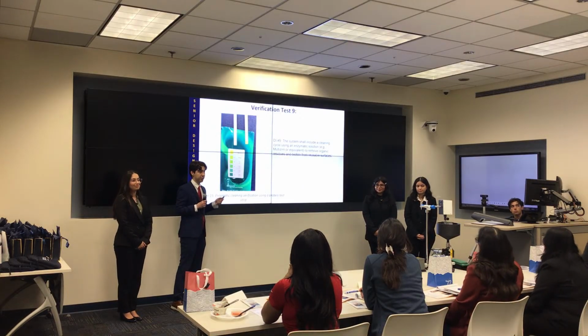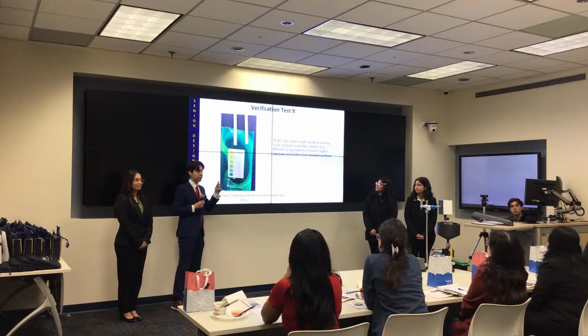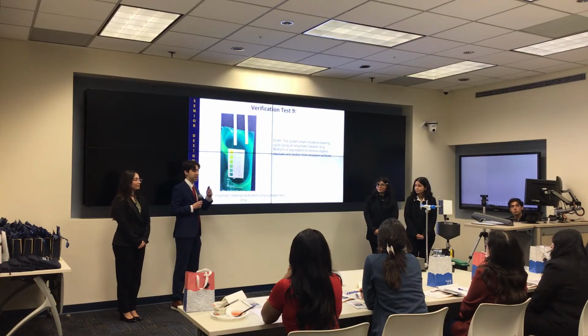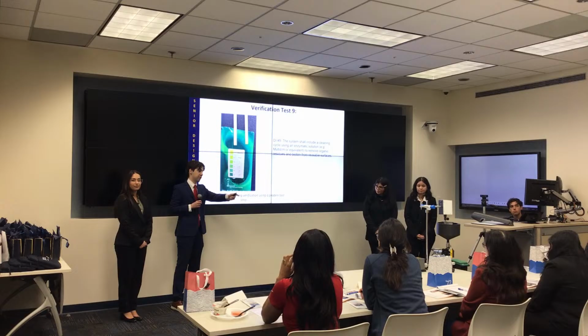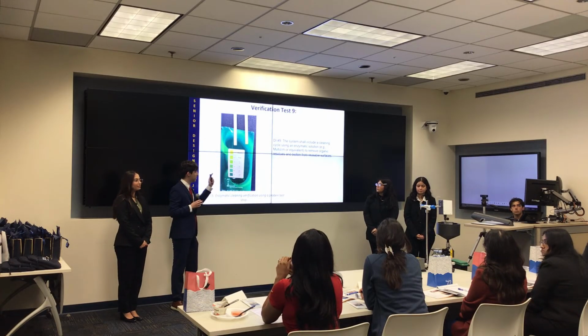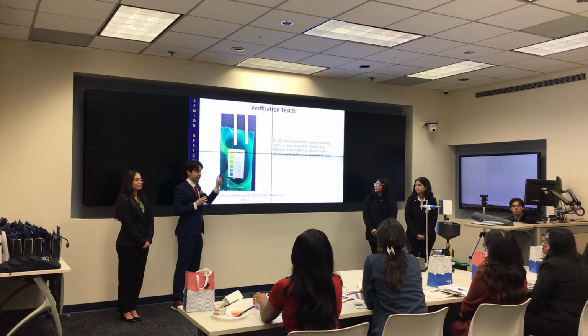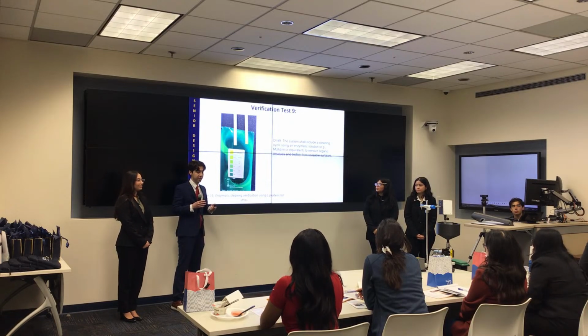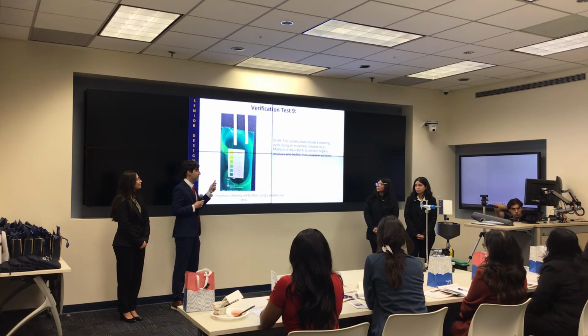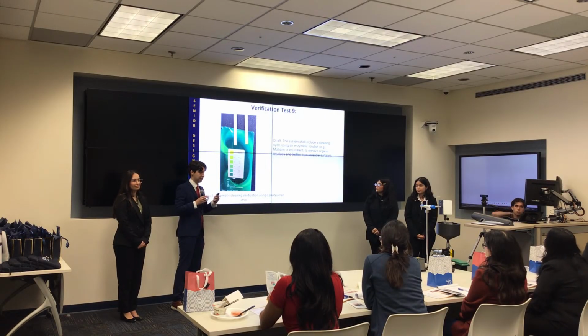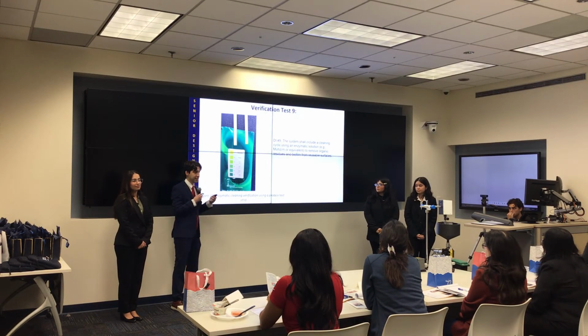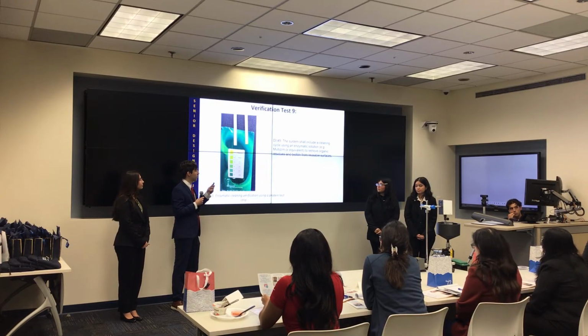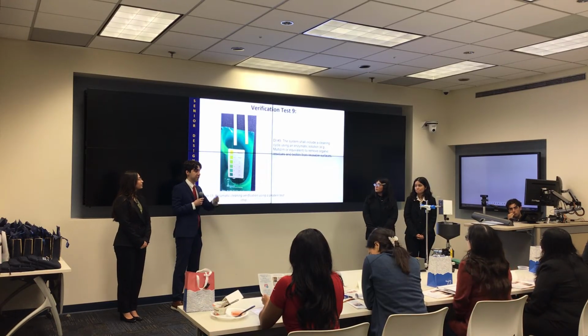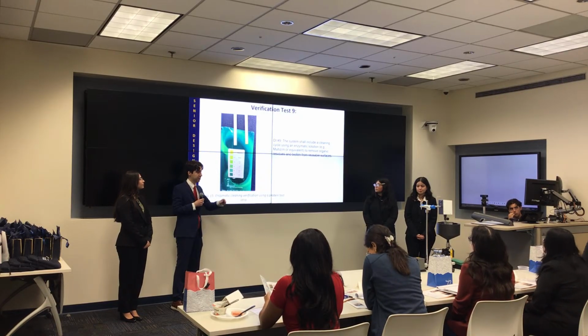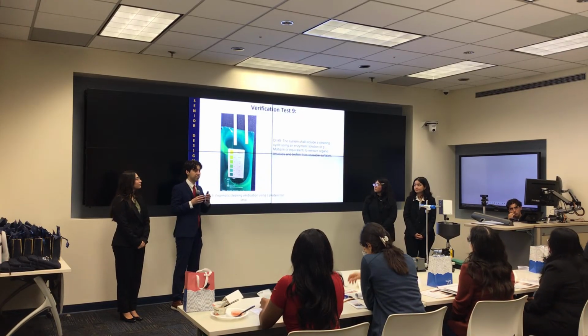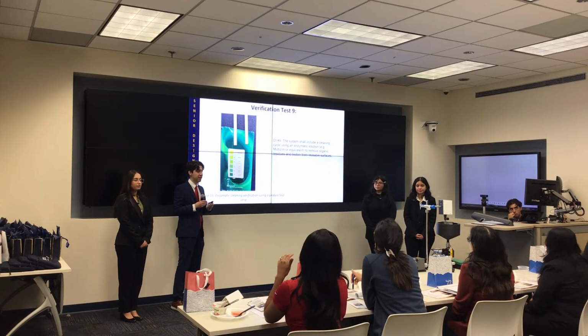Our next and final test was after each one of those 5 runs, we used protein test strips, which we applied to the filter within that chamber right there, judges. And you can see here that it, of course, came back positive because there was bacteria on the filter. This is expected. The problem is if we were to then run another sample through the system, there would be cross-contamination, and that could be very dangerous for the bacteria. So we used enzymatic cleaner, flushed it through the system, and then water to remove any leftover material, and it came back negative. We ran several more tests in order to ensure we could reproduce this, and struggled slightly.